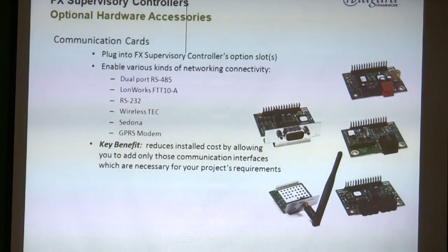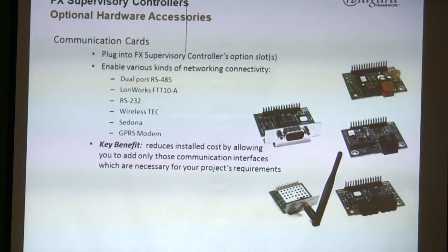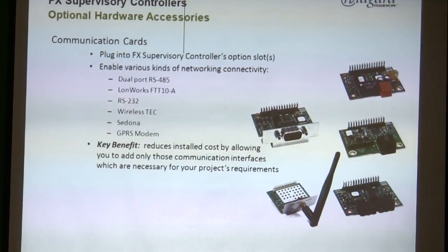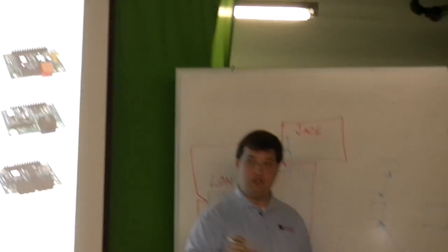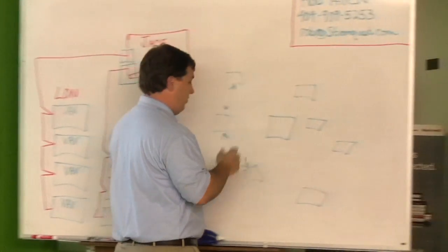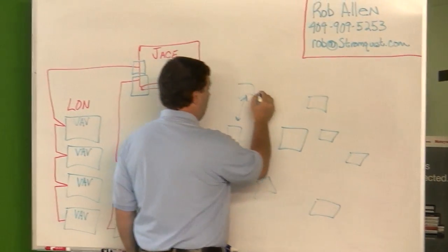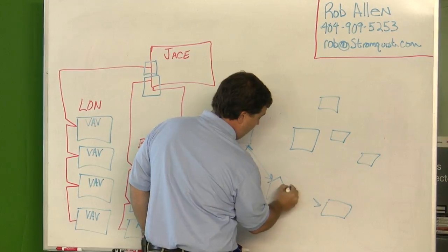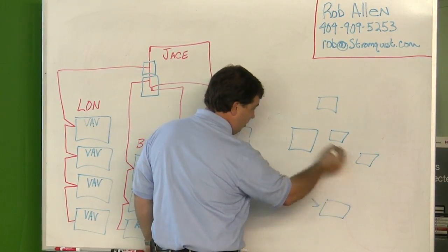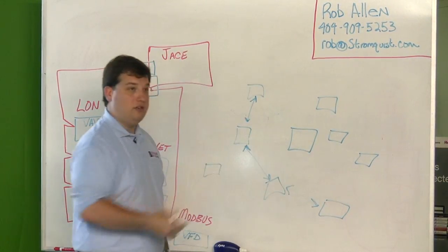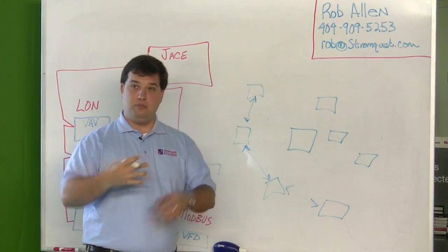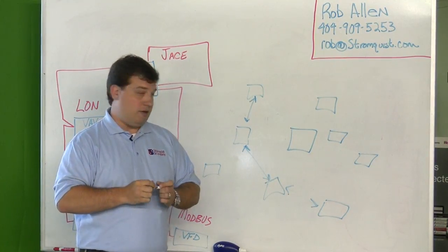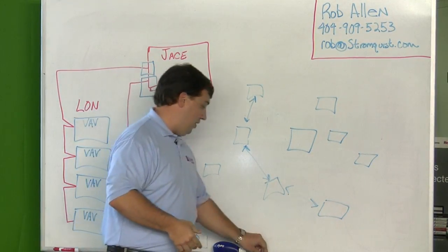If one node falls out, the system won't even let you set up unless you have three hops back to the coordinator with the TEC wireless. If this node loses connection, other nodes hop around and find a new path — it's a mesh system, and when things fall out, it pops back into place automatically.